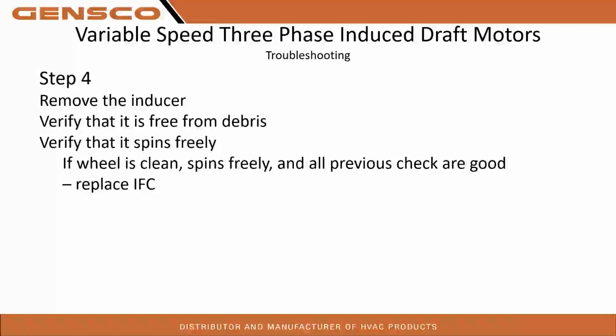So step 4, we're going to remove the inducer motor. We're going to make sure that it can spin and that it's free of any kind of debris. Make sure there's not a bird that fell down in the flue pipe, creating some problems, right? Verify that it spins freely, right? If the wheel's clean, spins freely, and all the previous checks are good, we're going to replace that IFC, right? We're going to replace the main control board.